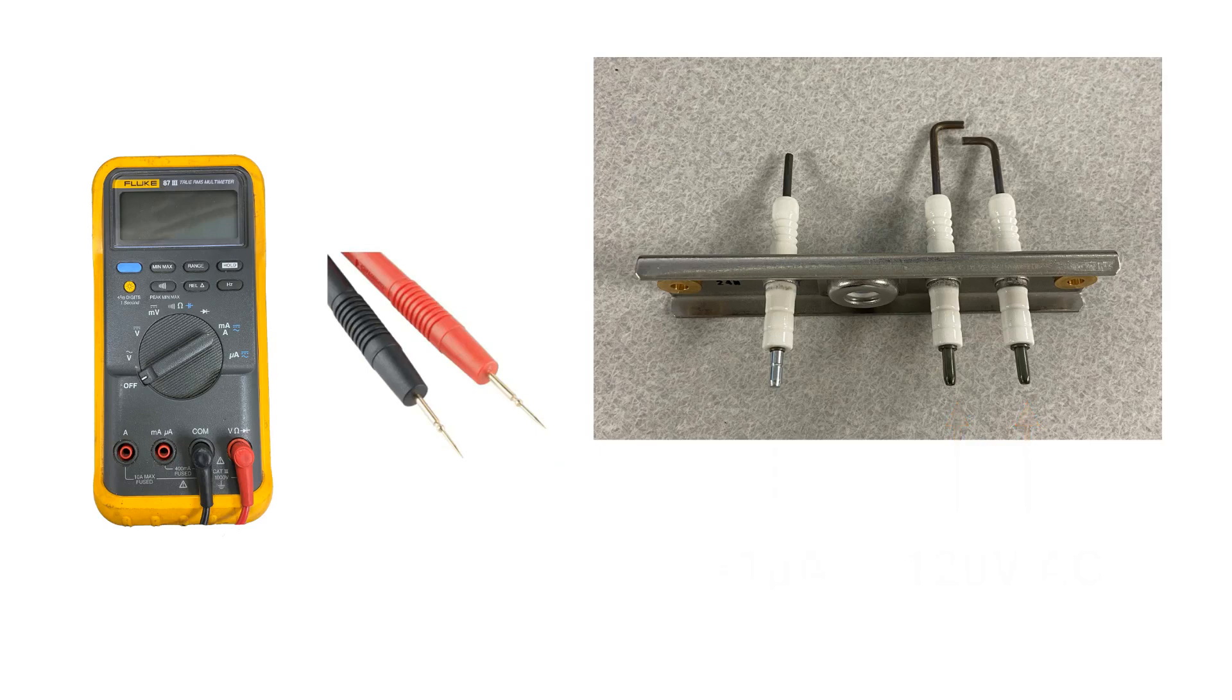To test the flame sensor, place your leads in series with the flame sensor lead. You should read greater than 1 microamp.